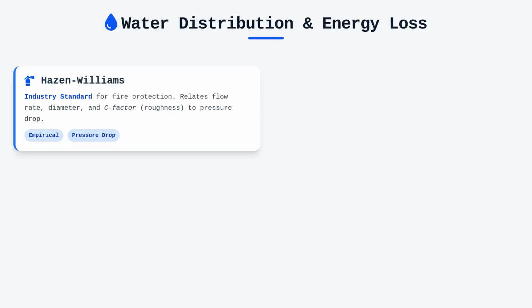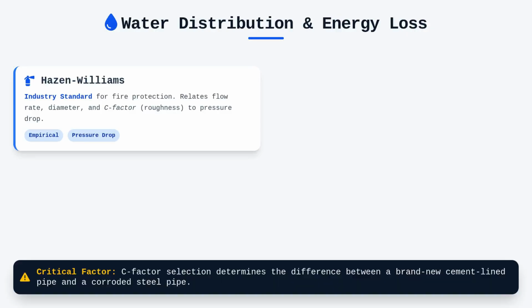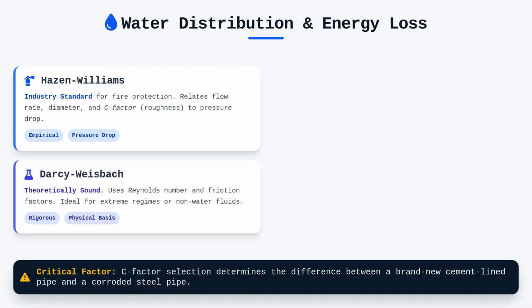Choosing the correct C factor, which represents the internal smoothness of the pipe, is critical, as a corroded steel pipe will exhibit significantly more friction loss than a brand new cement-lined ductile iron pipe. Darcy-Weisbach is more physically rigorous and theoretically sound, particularly for fluids other than water or extreme flow regimes, and it relies on the friction factor derived from the Reynolds number.